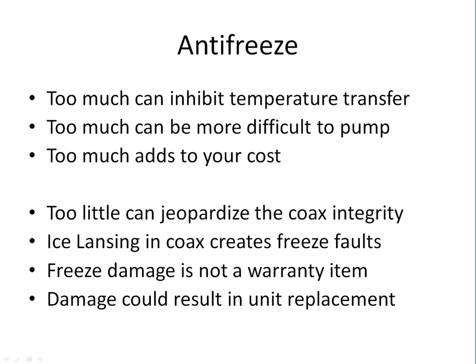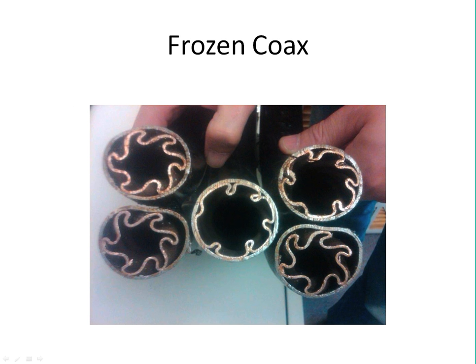Freeze damage is never a warranty item. We did not send you a geothermal heat pump with a frozen heat exchanger. Damage could result in unit replacement. Good for ClimateMaster, not so good for the homeowner and the contractor who didn't put in enough freeze protection fluid. So it's important to make sure that you put in the appropriate amount and you verify that amount.